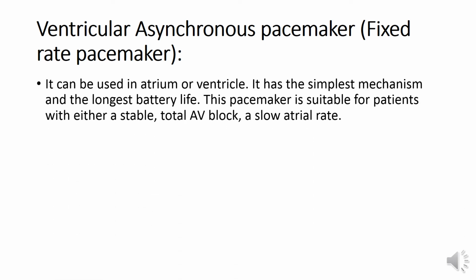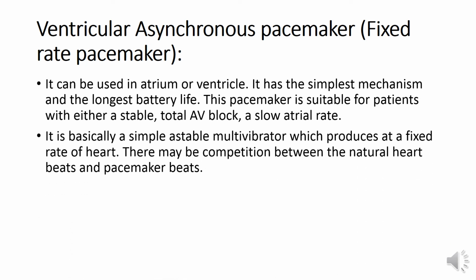This can be used on the atrium and ventricle side. It has the simplest mechanism and mainly has the longest battery life. This type of pacemaker is mainly suitable for patients with either a stable stage or total AV block and a slow atrial rate. In this method, we use the fixed rate pacemaker. It is basically a simple astable multivibrator which produces a fixed rate of heartbeat.